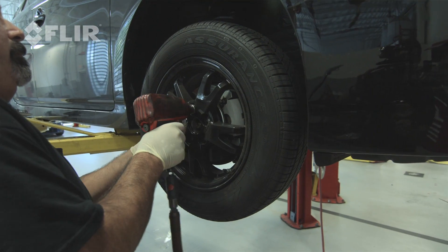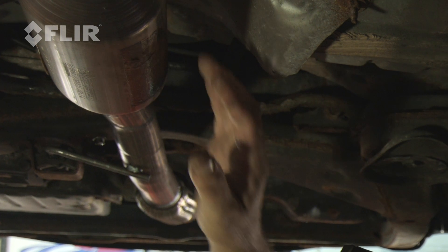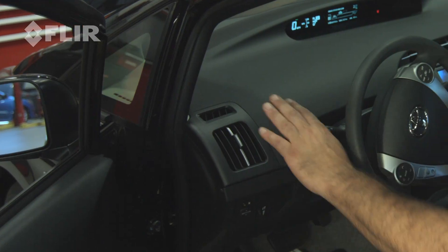Common issues — mostly it's routine maintenance, but we do find issues with exhaust systems and air conditioning and heating systems are very common issues. I use my spot temperature gun on the radiator to see if there was any blockage. I've used it on exhaust for the same reason, and we also use it for air outlet temperatures to see if air conditioning is working and the heat is working.